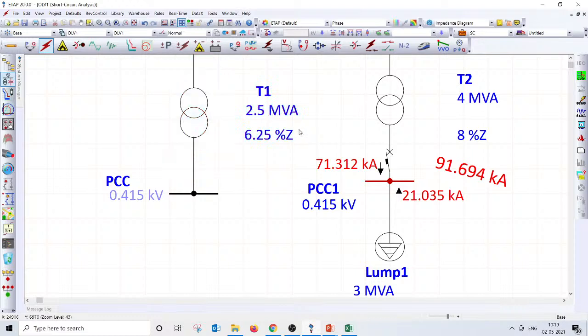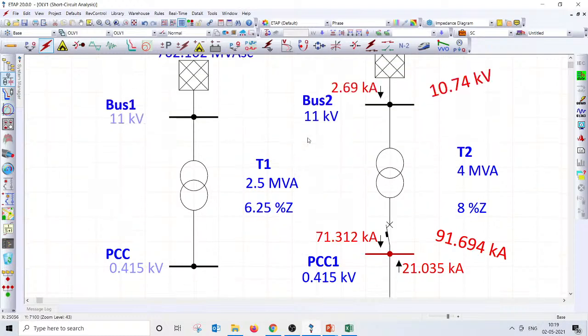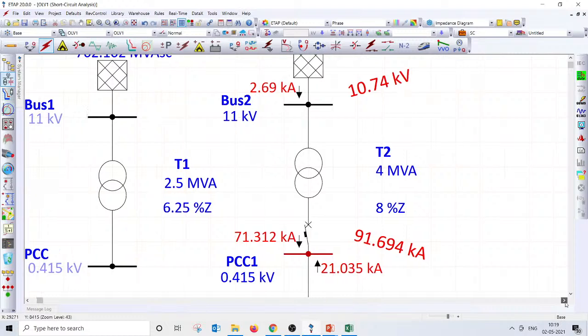But there are transformers available up to 3.15 MVA, even 3.5 MVA, which I have seen at 380 volt or 400 volt. Now assume that the load is, for example, 3.6 MVA or 3.7 MVA, then you may go with two 2 MVA transformers, which need two medium voltage circuit breakers. If you are familiar with solar farms, you might use another technique of three winding transformers or even multi-winding transformers, so that you reduce the number of switchgear requirements in the medium voltage.